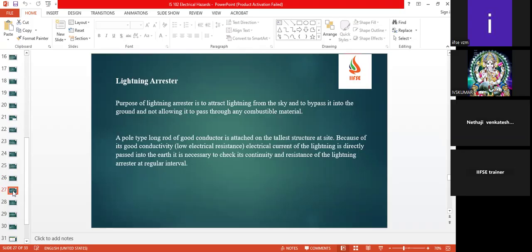Then lightning arrestor. When we say lightning arrestor, it is also a very good conductor to take the energy which is released from the atmosphere. The purpose of a lightning arrestor is to attract the lightning from the sky and bypass it to the ground, not allowing it to pass through any combustible materials. It is not about attracting. We are not wantedly asking the lightning energy to pass through our building or through our lightning arrestor.